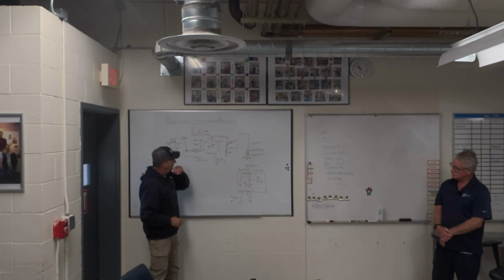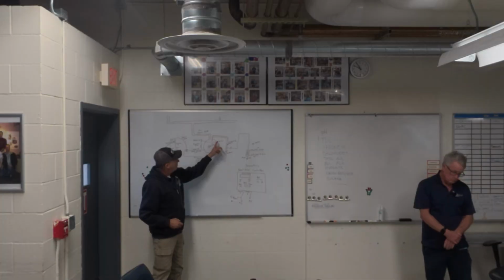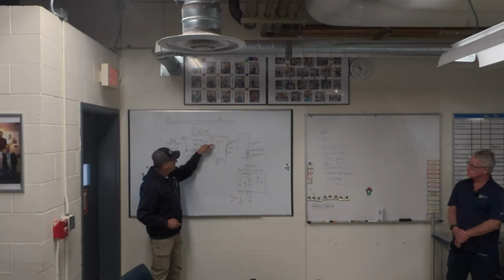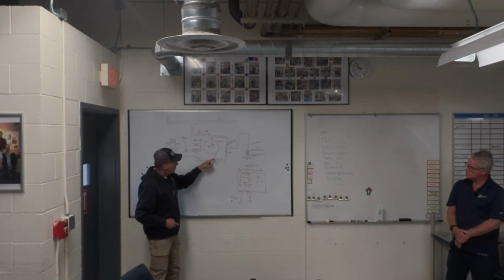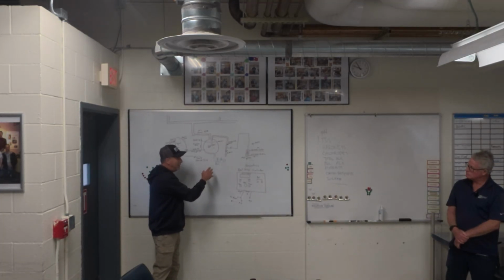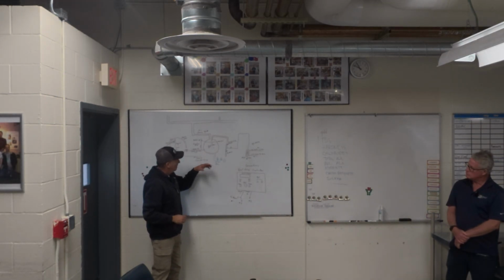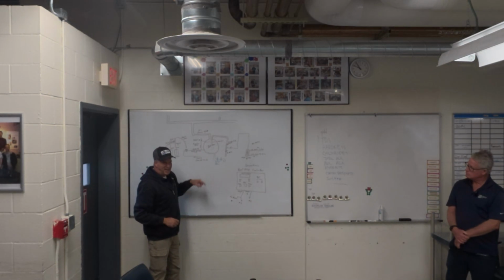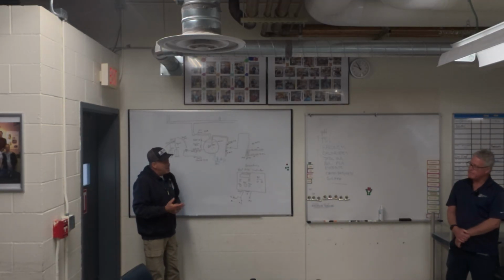Typically the conductivity sensor periodically senses the TDS and the chlorides in the top part, where the highest density of concentrated chlorides are. The other stuff reacts out and is managed periodically by a bottom blow. Those are the reactants, so when you get these out, the chemicals can actually do their work. If they accumulate in there, the chemicals will start working on them instead, it's like, no, get those out of there. Those are the reactants, so that's the idea, the way we see it.